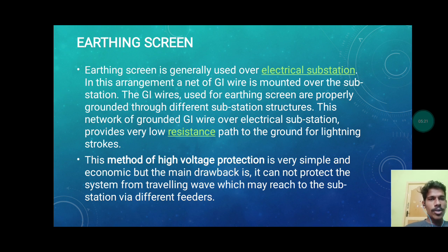The GI wires used for earth screens are properly grounded at different substation points. This network of grounded GI wire over electrical substations provides a very low resistance path to the ground for lightning strokes. Lightning strokes means thunder. Next point, this method of high voltage protection is very simple and economic, but the main drawback is that it cannot protect the system from traveling waves which may reach the substation via different feeders.